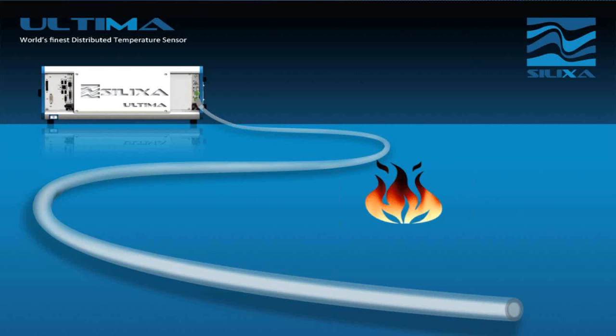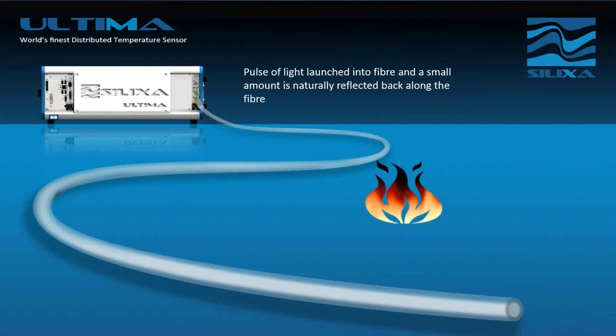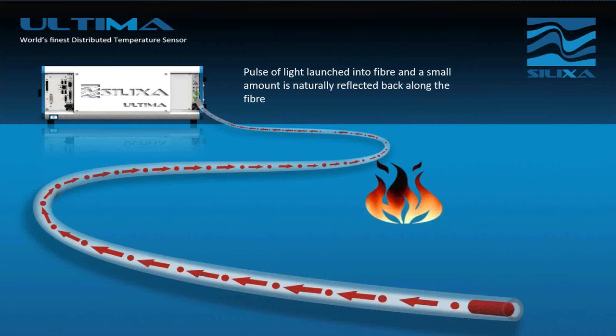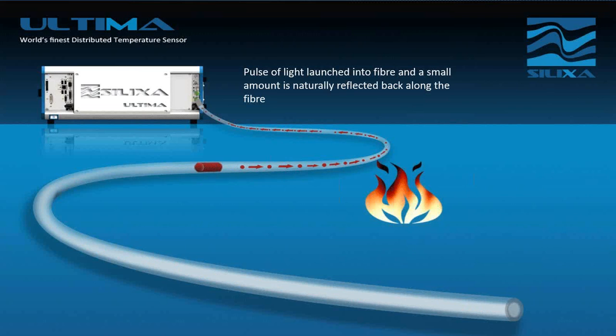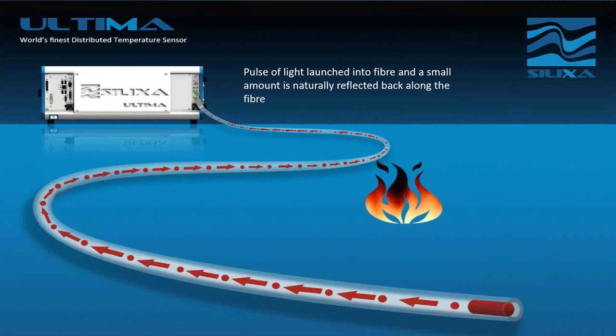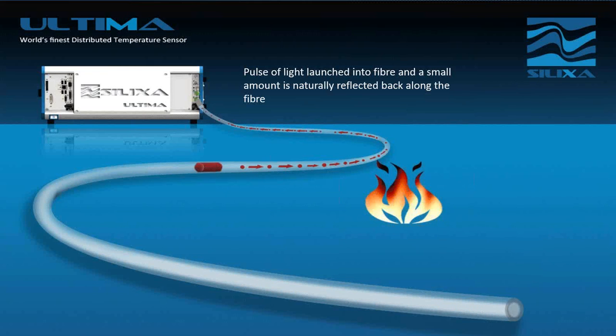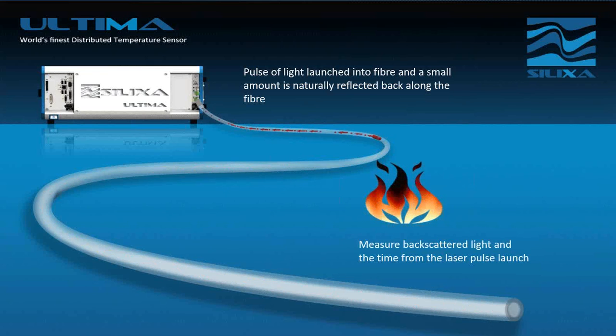The Ultima is the trade name for a distributed temperature sensor. It's a system constructed in the following manner and sends a laser pulse down the fiber. This is a standard optical fiber. We use a multi-mode gradient index fiber with the Ultima DTS, although we can also interrogate a single mode fiber.